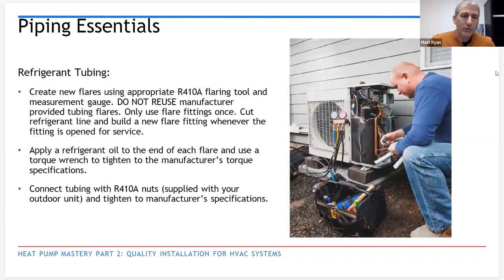Piping essentials when we're doing flares. We're never reusing the pre-made flare on the pipe. We're always making our own. Once you've tightened that flare down, it's a one-shot deal. So if it has to get disconnected for any reason, we are remaking that flare.